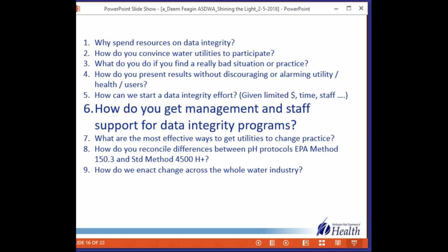Another example where you could do that is you could just take a picture of the turbidity controller screen, and you can often see on there the milliamps versus the NTU reading. You can take that picture back to the office, and you know it's a linear relationship. You can figure out if they're capping. It doesn't have to be in the moment, but you've collected that data.